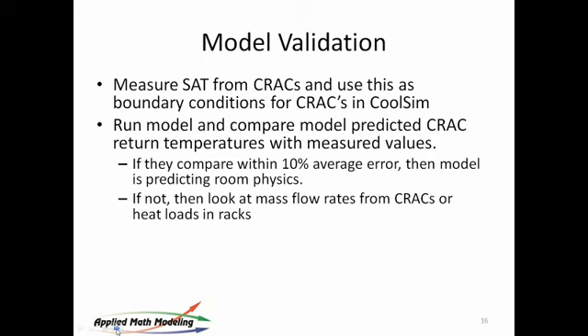Then we run the model. We compare the predicted CRAC return temperatures with the measured values. And if they compare within 10%, then the model is predicting the physics in the room fairly well. If not, then you go back and take a look at your equation and say, why not? Because if we have the return temp, the supply temp is fixed because we set that as a boundary condition.